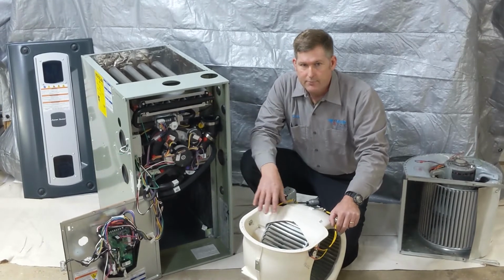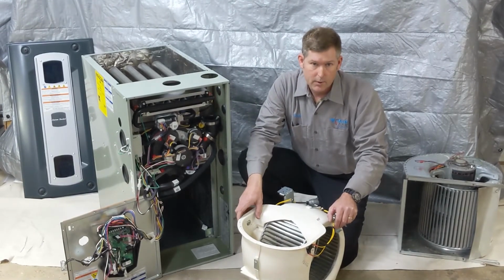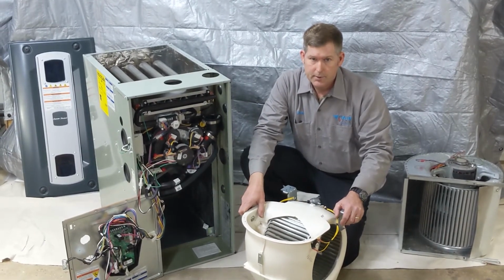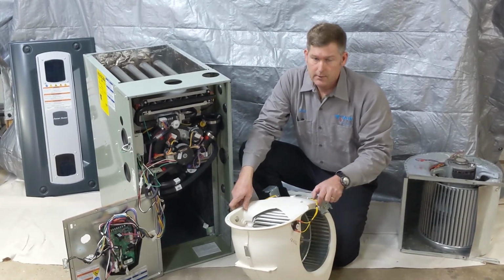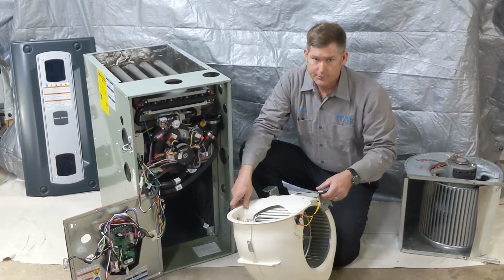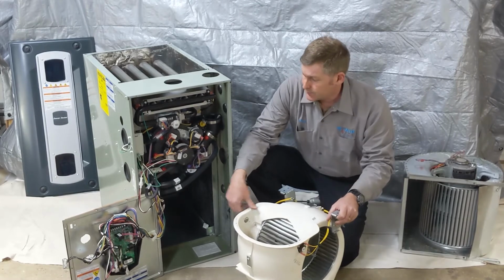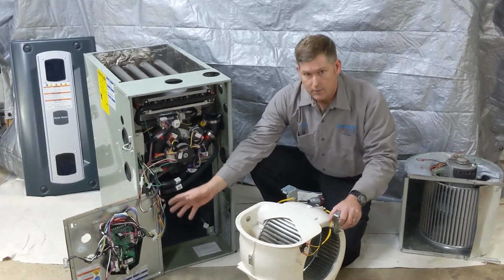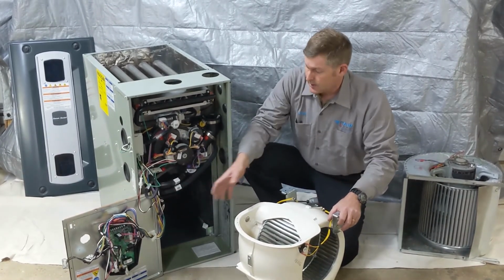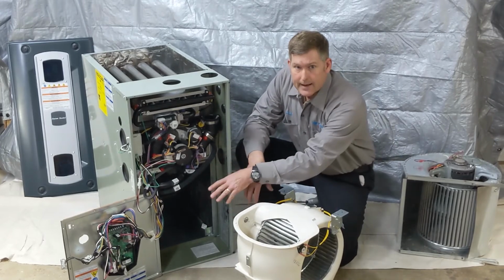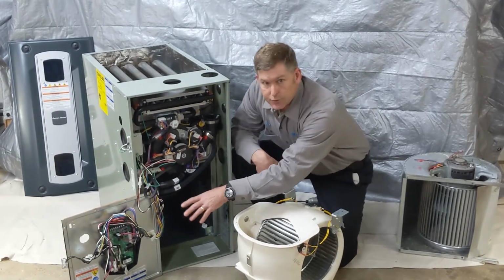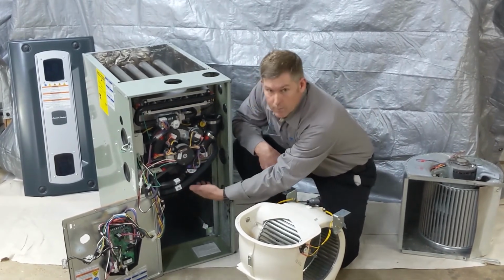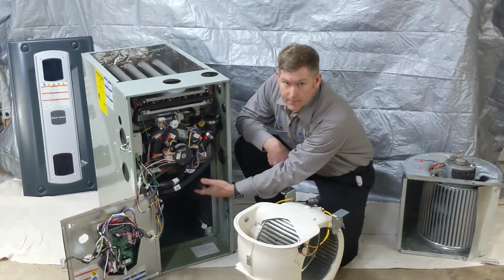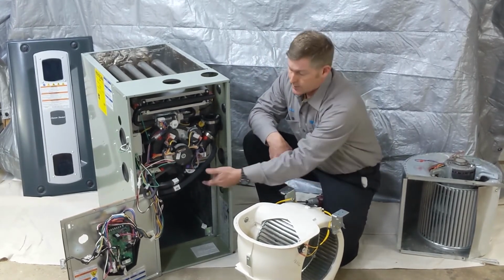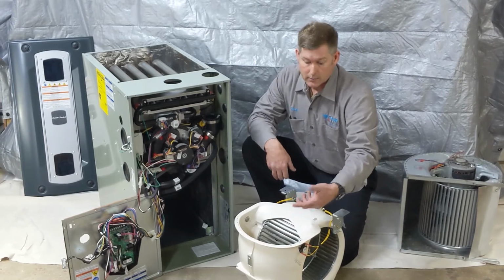My absolute favorite thing about this furnace is the blower motor. The ease with which you can get this thing out of the furnace and service it is just really simple. You can see down here I've got this front panel. I've removed a few screws. All the electronics stay attached to that panel. I just swing it out of the way. The blower motor is right here in the bottom part of the cabinet. I take out 2 screws. This whole thing slides out on rails.